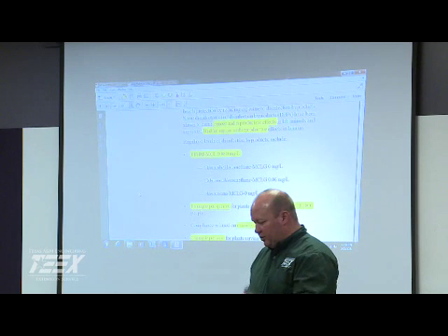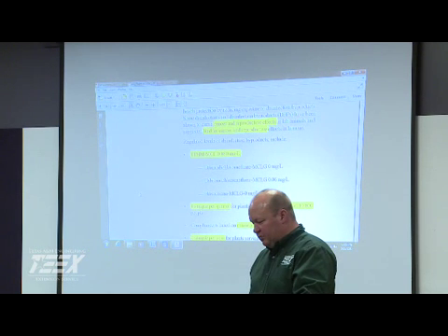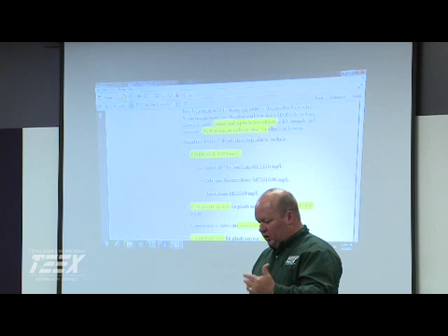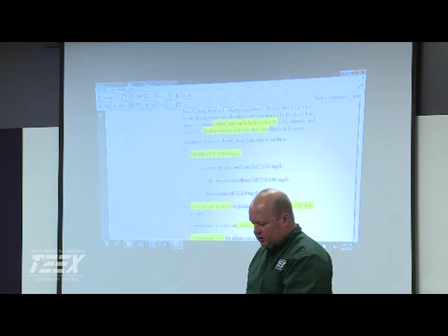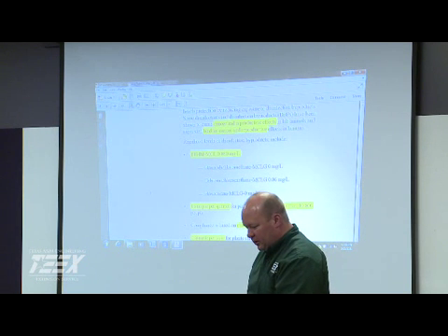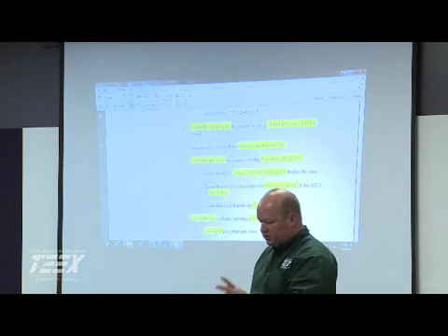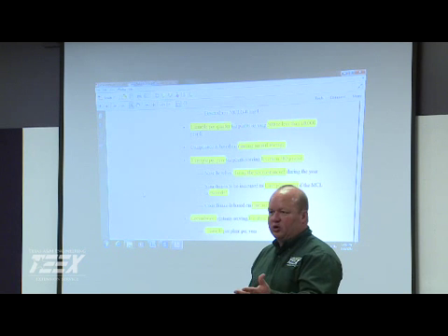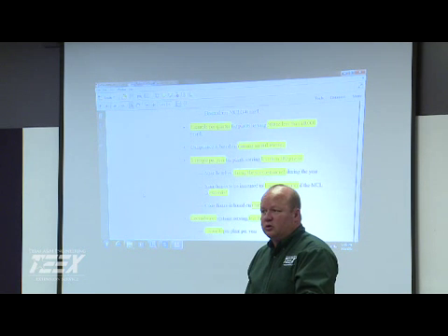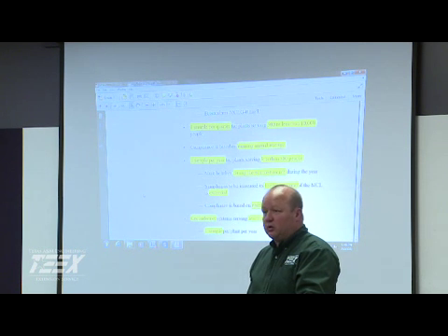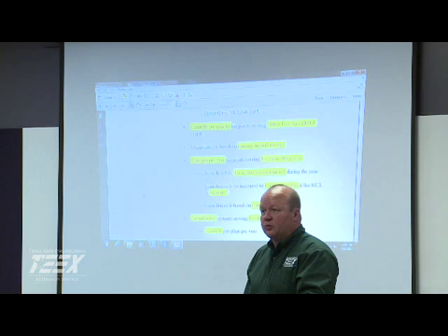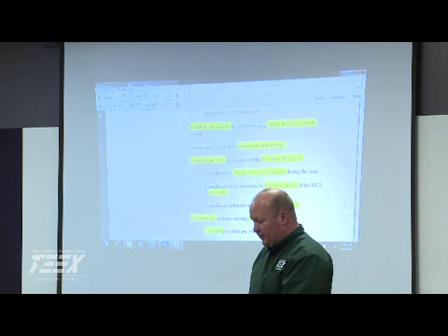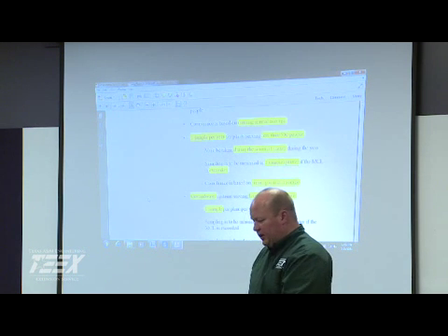The main thing again, we talked about with our disinfection byproducts, is the carcinogens. So our TTHMs, the MCL is 0.08, or 80 micrograms per liter. If you're a small system, y'all are just doing what? Are y'all still doing 1 per quarter on your total trihalomethanes? We've got 4 sample sites on THMs and acids, per quarter. Okay. Good. And then, like I say, here it's the running annual average.